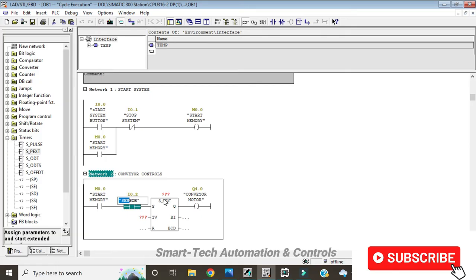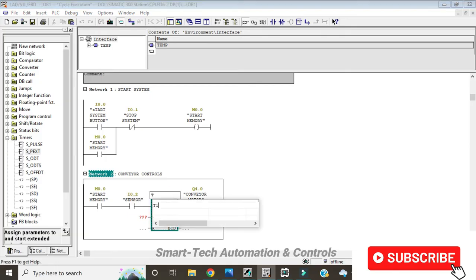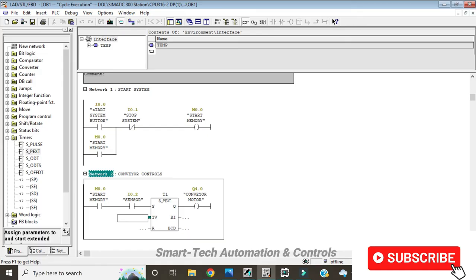We then have the timer. Let's call it T1. This TV here is the time value. And this is where we set the duration after which the conveyor goes off if the sensor does not detect a product. I'll give it a value, S5T#10S, where the 10S represent 10 seconds.